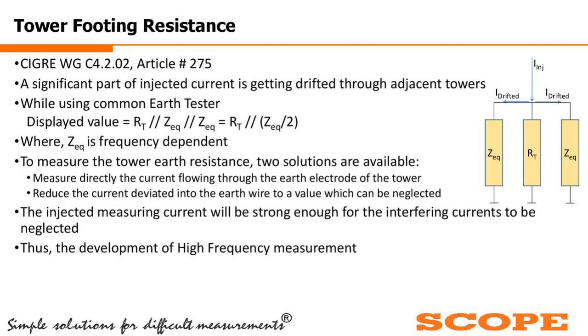But then what value will I be getting? I will be getting RT, the tower footing resistance, in parallel with the equivalent resistance Z equivalent of the two adjacent towers, in parallel with the other adjacent towers, in parallel with the n number of adjacent towers. If we neglect all other things for the time being, or club all the Z equivalent things on the left hand side and right hand side, then we get two Z equivalents. So RT in parallel with Z equivalent 1 and Z equivalent 2. And if we consider those two values of equivalent resistance or impedance to be the same for the left hand side and right hand side, then we can say the displayed value will be RT in parallel with Z equivalent by 2.